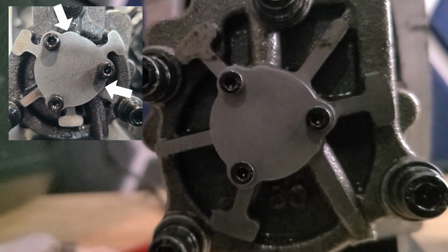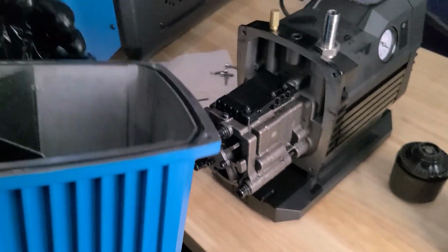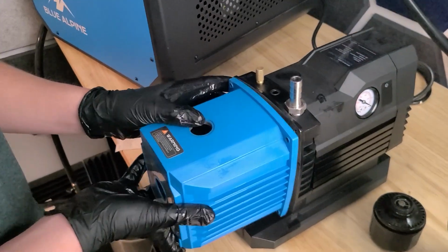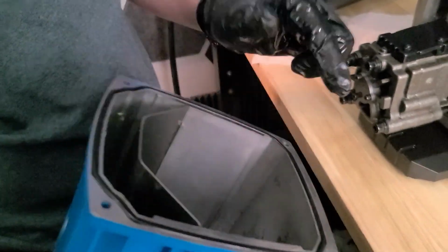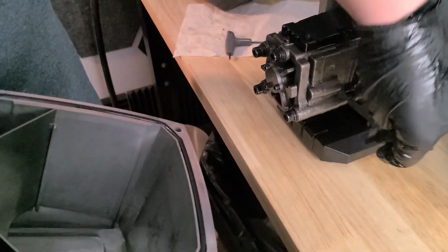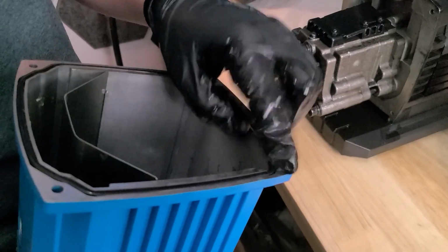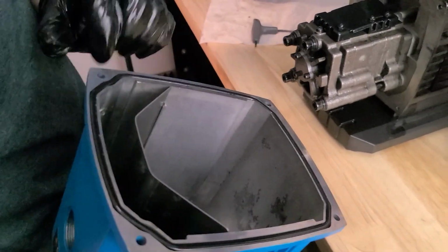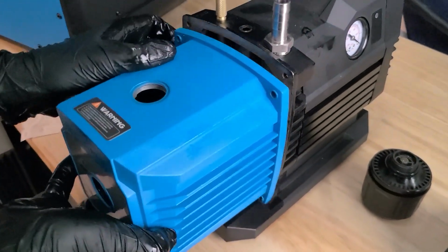The next step you are going to want to do is take your vacuum pump cover and put it back on. You're going to want to make sure when you're putting this back on that this O-ring stays set in place. If this O-ring can come out, it will cause leakage. So make sure the O-ring sits in there so that when you tighten this thing down fully, your vacuum pump is not leaking.